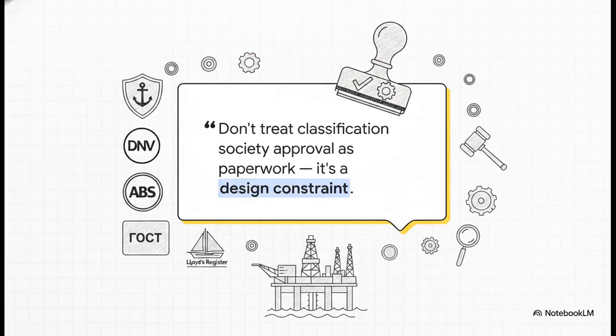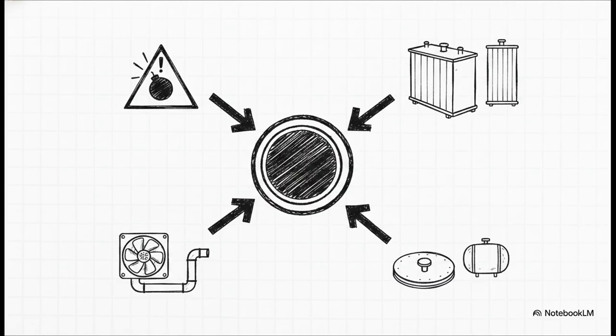Our third design axis is a bit of a harsh regulatory reality check. You absolutely must adhere strictly to the classification society approvals that govern your specific offshore rig, whether that's DNV, ABS, or Lloyd's Register. But whatever you do, please do not make the mistake of treating these class approvals as mere administrative paperwork to be checked off at the very end of a project. Because that class approval literally shapes the physical asset from the ground up. I mean it. If you wait until the end of the line to check these requirements, you're going to find yourself completely re-engineering the transformer after the fact.